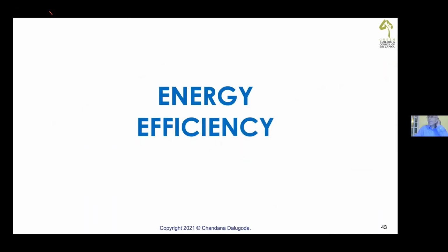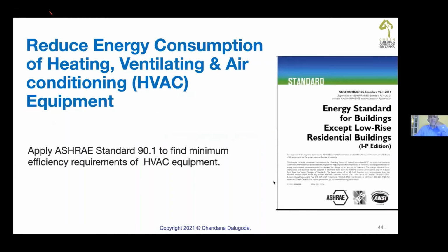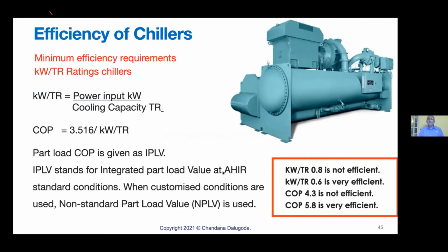Next focus is energy efficiency. 90.1 has an energy efficiency section. Now, whatever HVAC equipment we use has to be really energy efficient. If you take a commercial building, 60 to 70% goes for the air conditioning system plus lighting and a few others. So the prime importance is to have energy efficient equipment. Equipment energy efficiency is given as kilowatt per ton or COP, coefficient of performance.